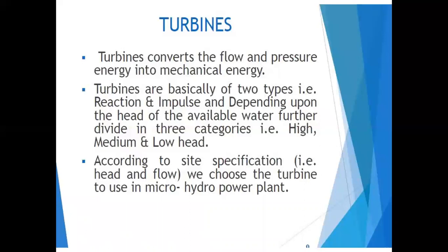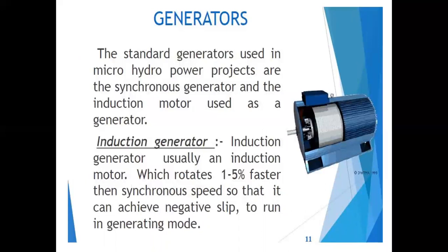The standard generators used in micro hydro power projects are the synchronous generator and the induction motor. These are all AC generators. The induction generator runs one to five percent faster than the synchronous speed so that it achieves negative slip to run in generating mode.